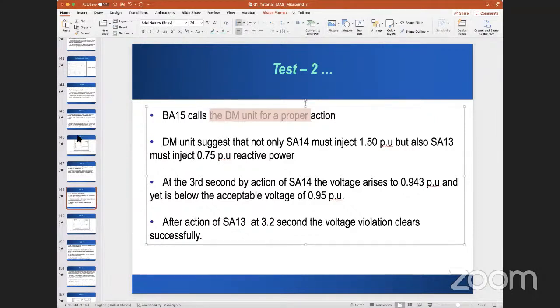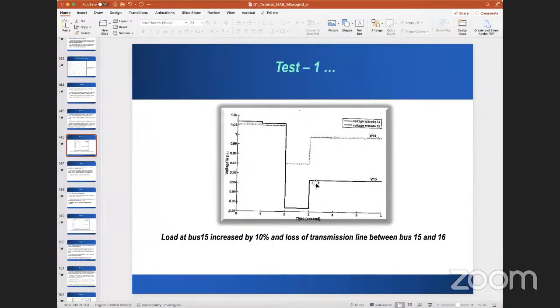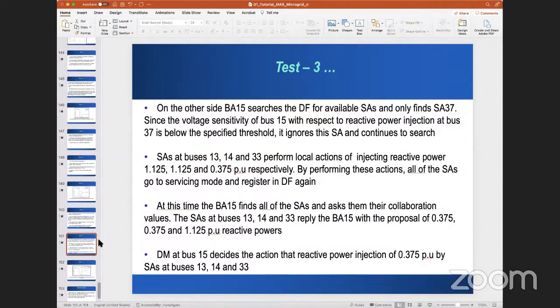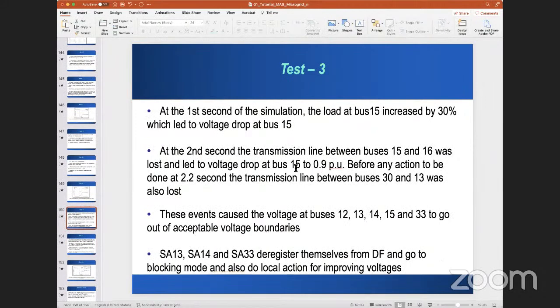If you can see that clearly, in scenario 1, when we had a 10% increase in the load, our voltage went here, and by injecting 1.5, probably that may be the max limit of the STATCOM at bus 14, right? So bus 14 is engaged, and we are just barely reaching the lower side limit of the voltage at bus 15. So it makes sense that we probably will need 2 STATCOM here. Okay, sorry, we were here.